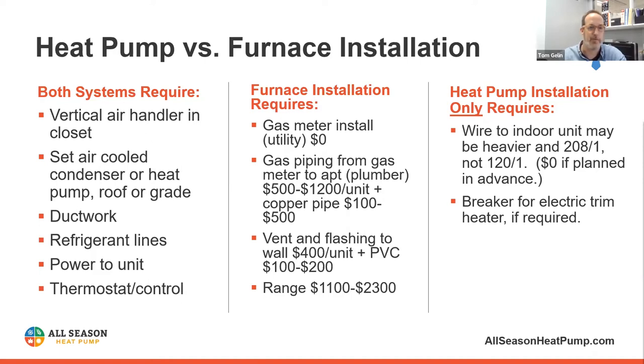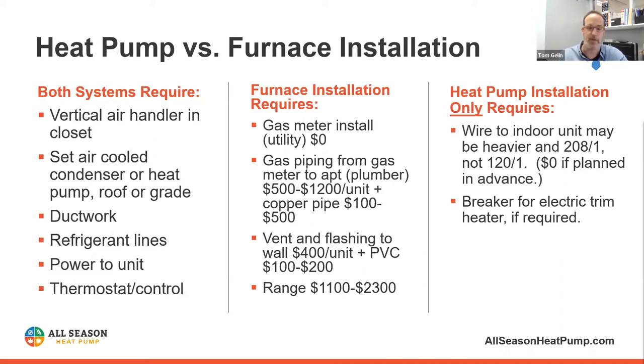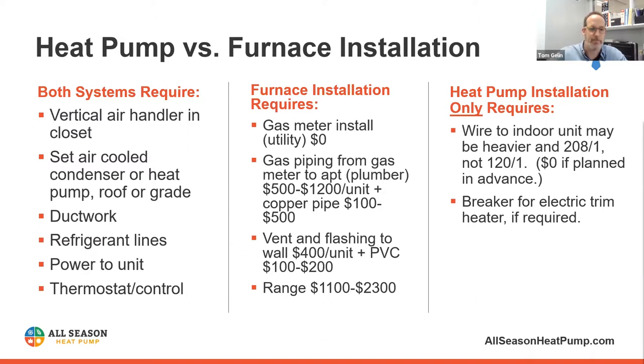So how close are we going to be with the heat pump? There are a couple of small differences. The furnace is usually 120-volt; the heat pump indoor air handler is 208-volt single-phase. If we know about this in advance, that should be a zero-dollar difference. Also, it is a good idea to have some trim heat — not absolutely necessary — and if we need an extra breaker for the trim heater, that may be a small charge. But if planned in advance, the electrician should not be charging a lot. It really boils down to the gas pipe and vent being the expensive items.